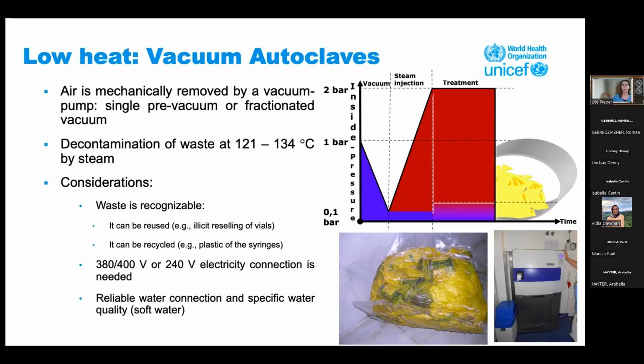So starting with the vacuum autoclave. Talking about vacuum autoclaves, it is important because the vacuum really ensures that the air is sucked out of the system, so that there's no air in the chamber anymore, and that all waste can be in contact with the steam which is inserted into the system. This is why WHO is recommending to use a vacuum autoclave instead of the gravity autoclaves. So the process is based on heat, vacuum and steam. The waste is decontaminated at temperatures between 121 and 134 degrees. By doing this, all the germs and pathogens are killed.